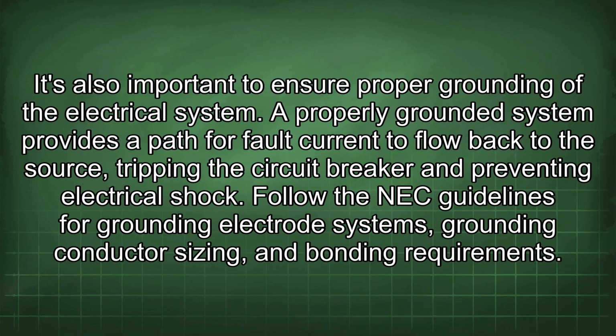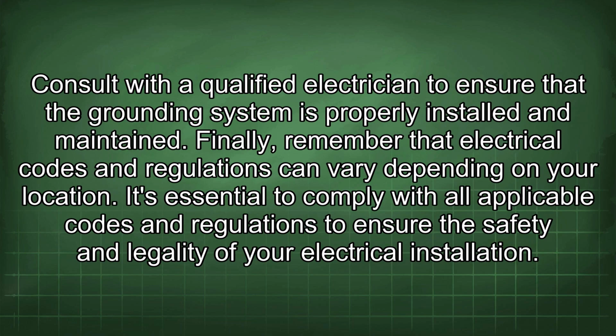It's also important to ensure proper grounding of the electrical system. A properly grounded system provides a path for fault current to flow back to the source, tripping the circuit breaker and preventing electrical shock. Follow the NEC guidelines for grounding electrode systems, grounding conductor sizing, and bonding requirements. Consult with a qualified electrician to ensure that the grounding system is properly installed and maintained.